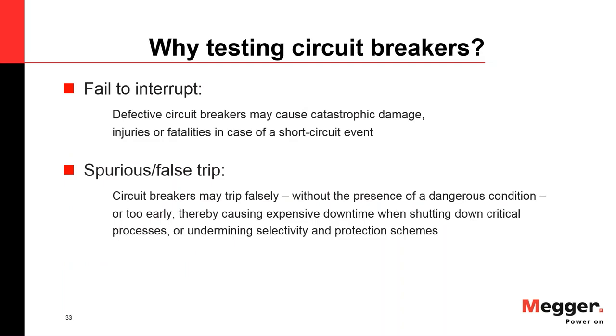Why are we talking about testing circuit breakers, and what could be the danger? Well, if the circuit breaker fails to interrupt for whatever reason, it can be a disaster. People can get hurt or killed. For me personally, I would make it mandatory that every person that works in the power industry goes to a test lab and watches some of the interruptions and some of the testing that is being done during the type testing. Because once you see what happens when a circuit breaker interrupts or fails, there's no discussion about why we are testing and should we test. Nobody wants to be in front of a fireball and be killed by that.